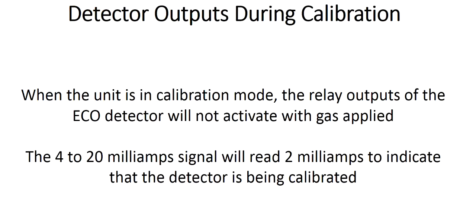When the unit is in calibration mode, the relay outputs of the ECO detector will not activate with gas applied. The 4 to 20 milliamp signal will read 2 milliamps indicating the detector is in calibration mode.